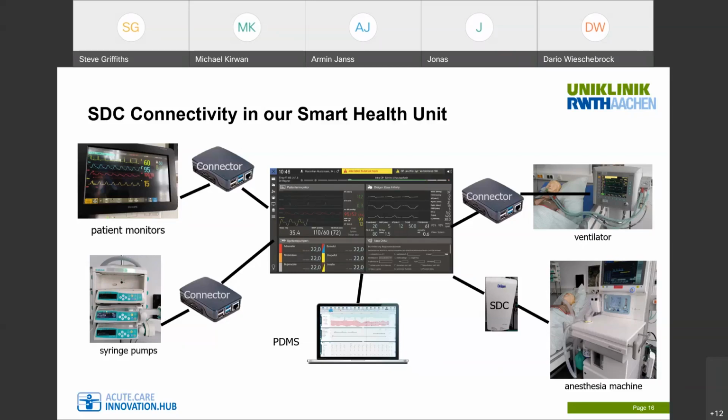And there you have either a provider or a consumer side, which is filled with data from the medical device, which you get over the other interface translating the proprietary protocol. But this SDC interface does not only care for providing the data, but also has the protocol for communication concerning invocation state or change requests that they're processed according to the standard.